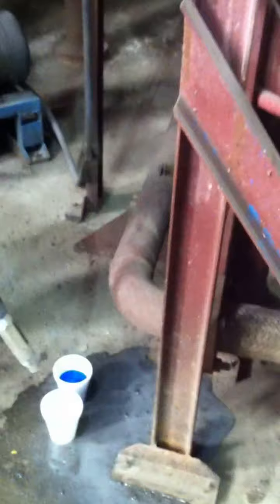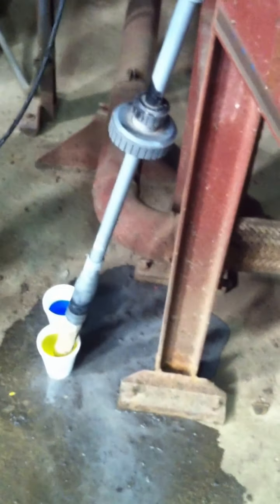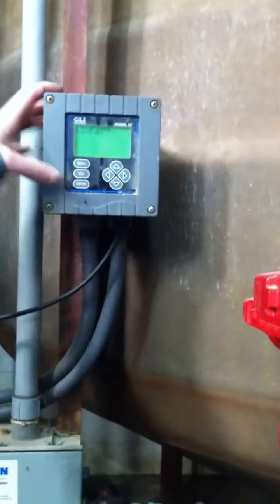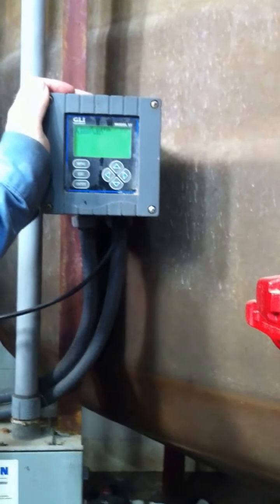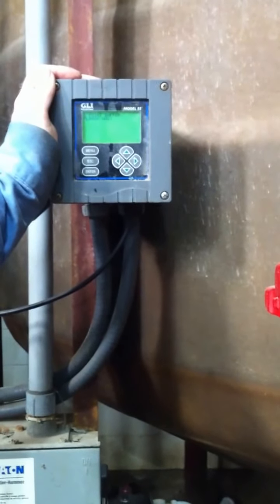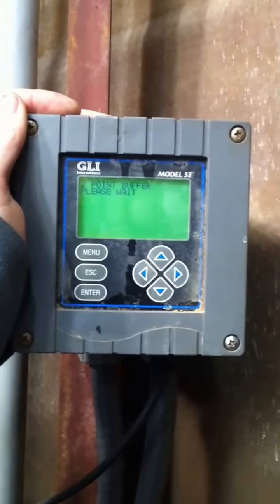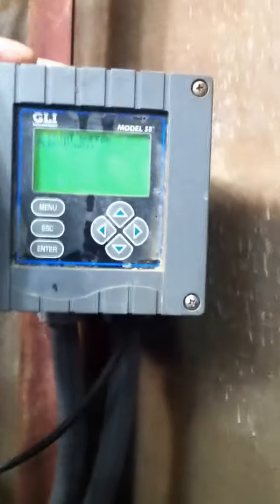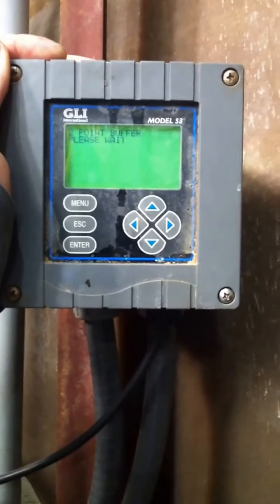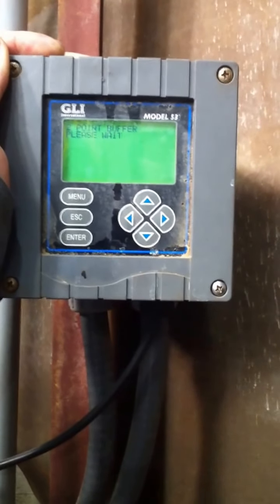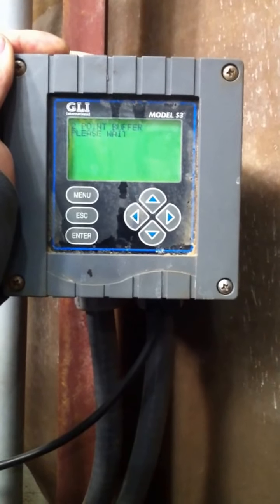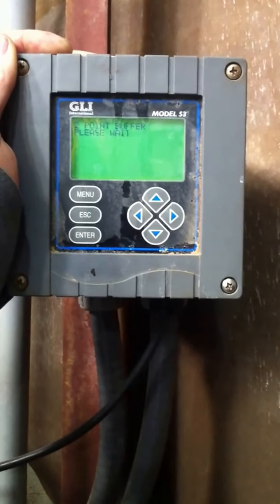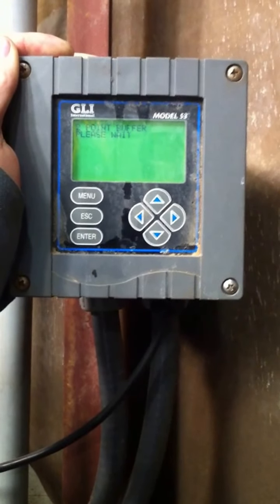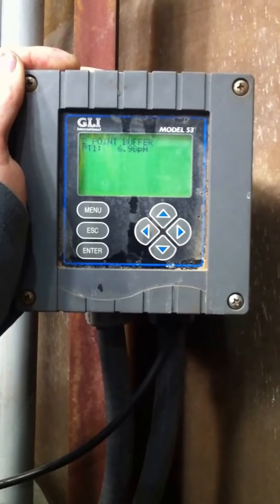So I'm going to place a probe in the 7 solution, lean it back, and then I'm going to go ahead and push enter on the controller because it's asking if it's in the first solution, and it's going to wait until it sees that at a 7 pH. This may take a little bit of time. Okay, so it's reading a 6.98 on point 1.